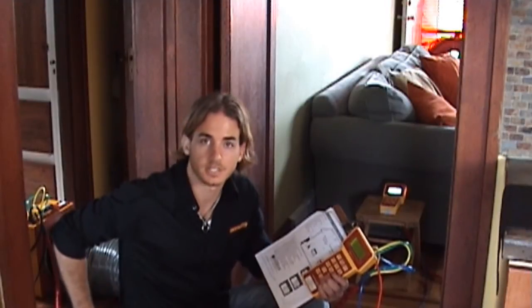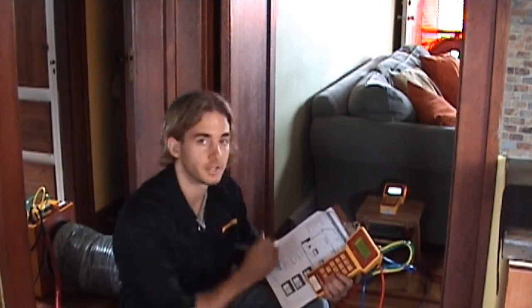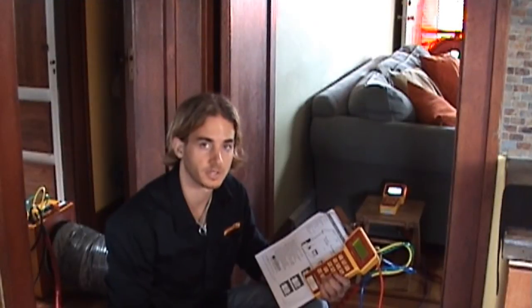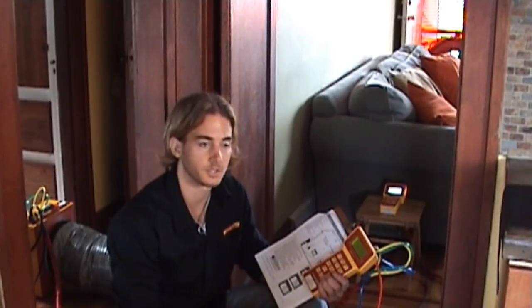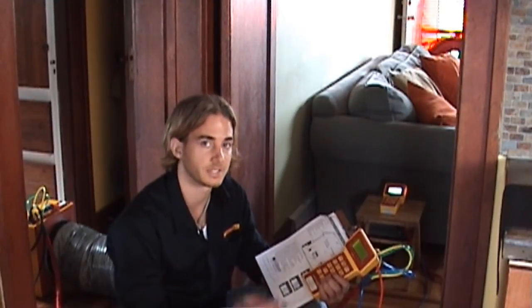I'm here set up today to do a duct leakage to the outdoors test. What I've got set up behind me is the DU220 duct tester as well as the Retrotec door fan and the front door. The idea is to neutralize any leakage between the ducts and the inside of the house by eliminating any pressure difference. The door fan will achieve a zero Pascal pressure difference between inside the house and the outside, and the duct tester will achieve 25 Pascals relative to the outside.